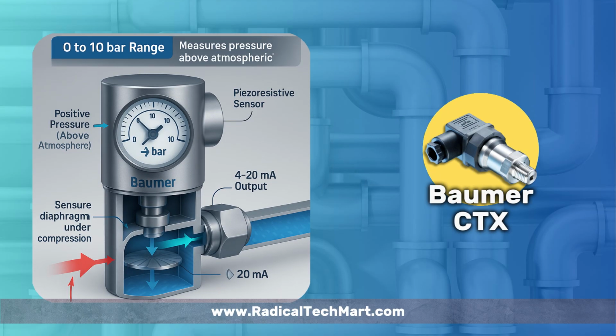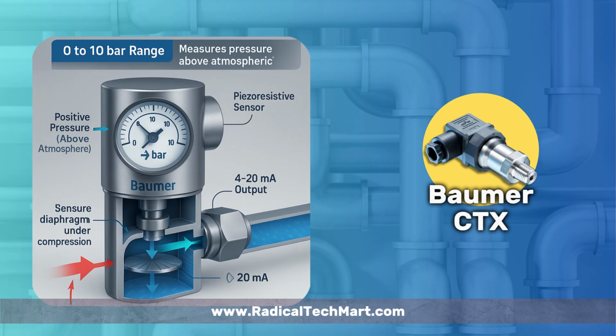A range like 0 to 10 bar means the sensor measures pressure above atmosphere. But a range like -1 to +9 bar covers both vacuum and positive pressure in the same device. This is very useful in systems that operate in both directions, like refrigeration, pneumatic testing, or vacuum packaging. If your system pulls a vacuum before pressurizing, go for a negative range model such as CTX -1 to +9 bar or -1 to +24 bar.